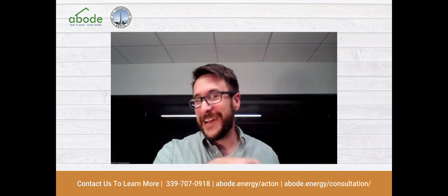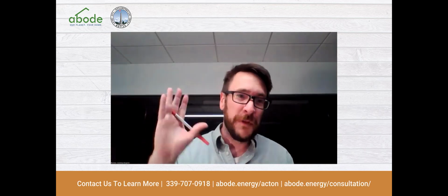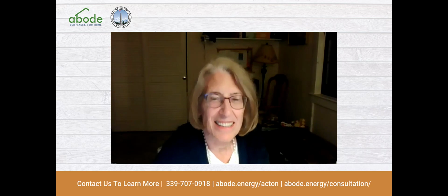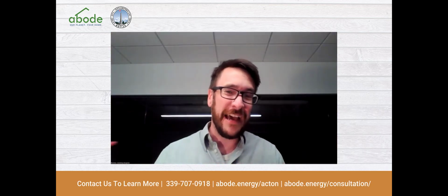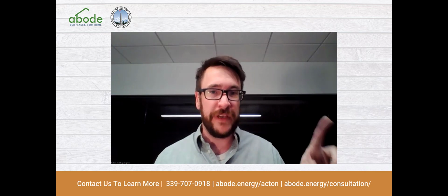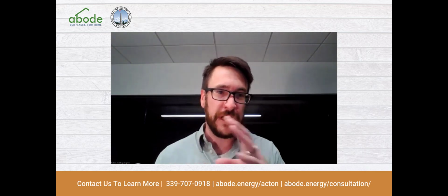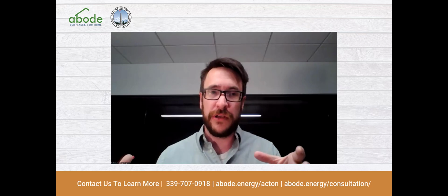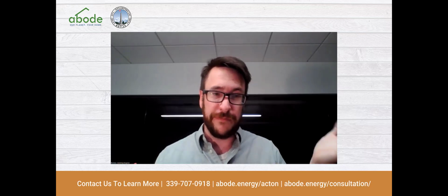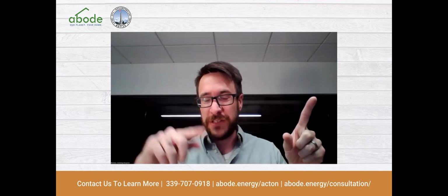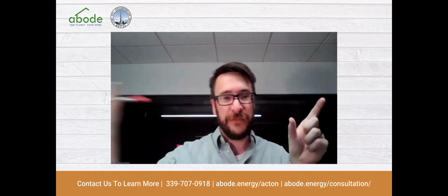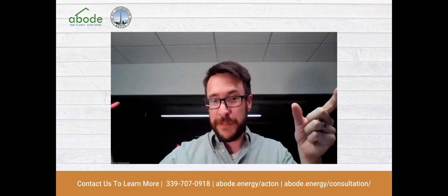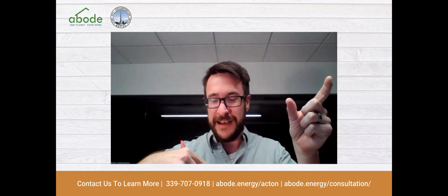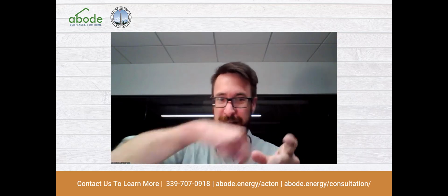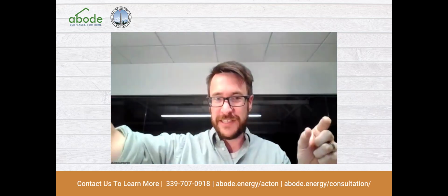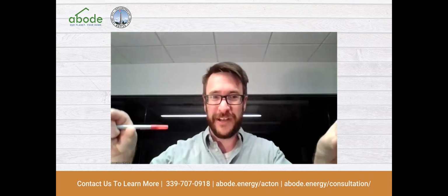Going back to the idea that a BTU is a BTU is a BTU, that still holds true. You're likely looking at a different type of heat pump, something like a VRF, variable refrigerant flow system, with a much bigger outdoor unit and more configurations of indoor units. They can do cool things, like one unit calling for heating while another calls for cooling, sending energy from one indoor heat pump to another instead of dumping heat outside and picking it up again.